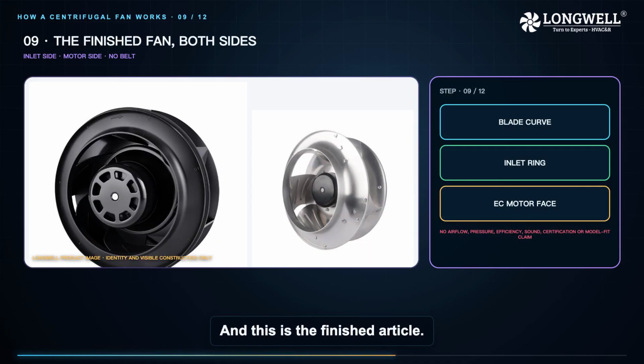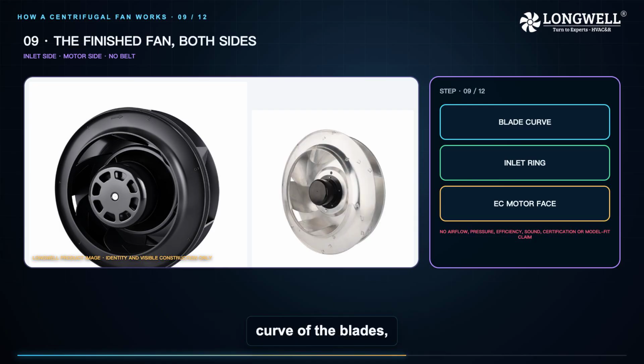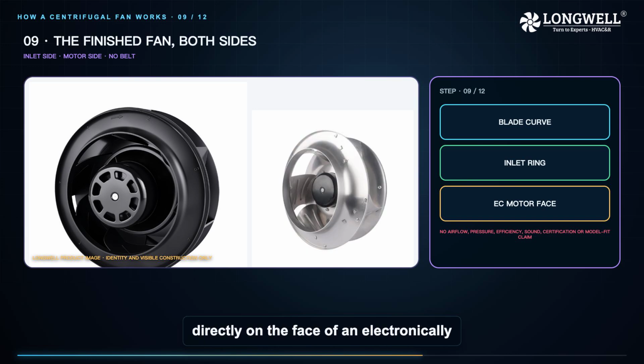And this is the finished article. From the inlet side you can see the curve of the blades, the inlet ring, and the cast rotation arrow. Turn it around and the wheel is sitting directly on the face of an electronically commutated motor, so the rotor and the impeller are one assembly, with no belt, no coupling, and no separate drive.